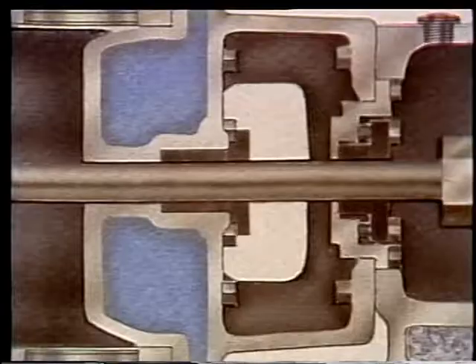Insufficient flow can often be corrected by adjusting a valve. If it can't be adjusted to the right flow rate, you'll probably have to stop the compressor and clean out the intercooler water jackets and their water lines.